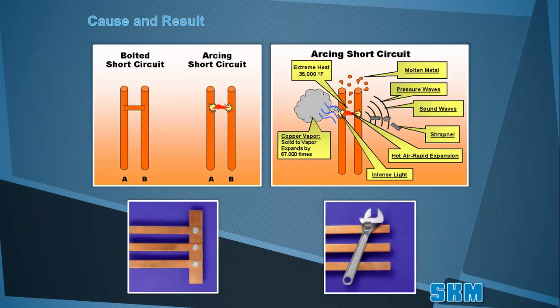Arcing faults occur when the current passes through the vapor between two conducting materials. These high temperature arcs can cause fatal burns even when standing several feet from the arc. The electrical arcs also shower droplets of molten material in the surrounding area, causing further hazard. The arcing fault current is smaller than a traditional bolted fault current because the vapor acts as an impedance between the conducting materials.